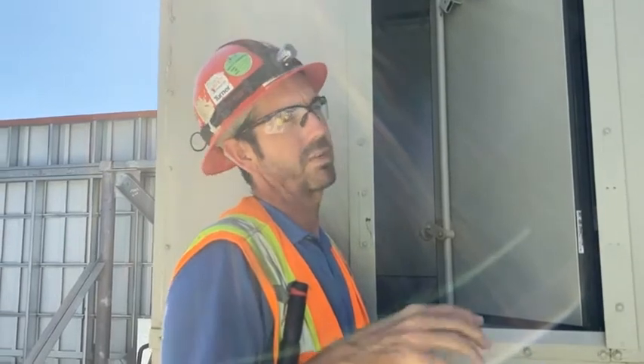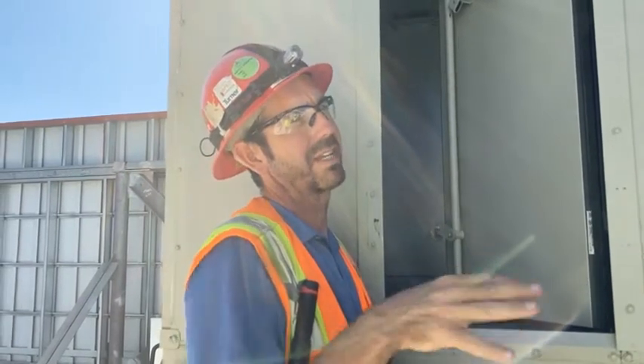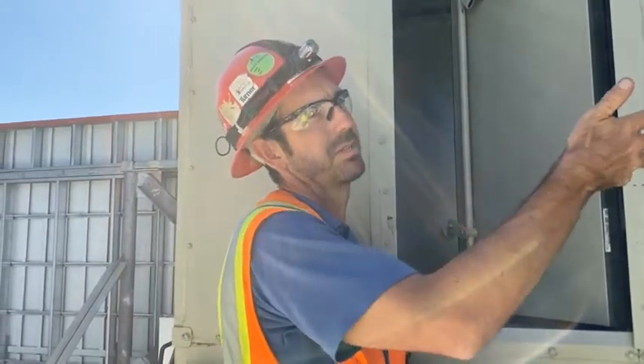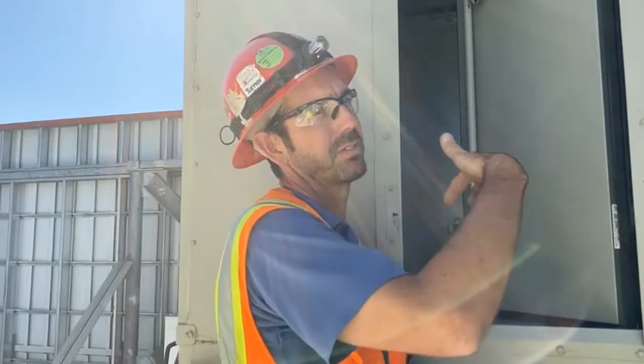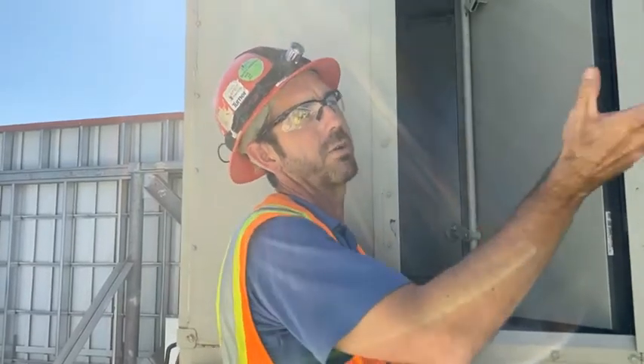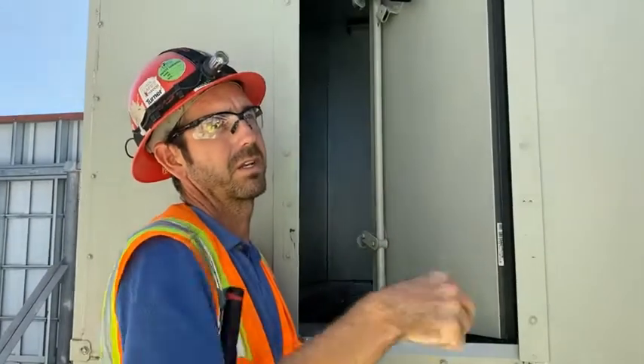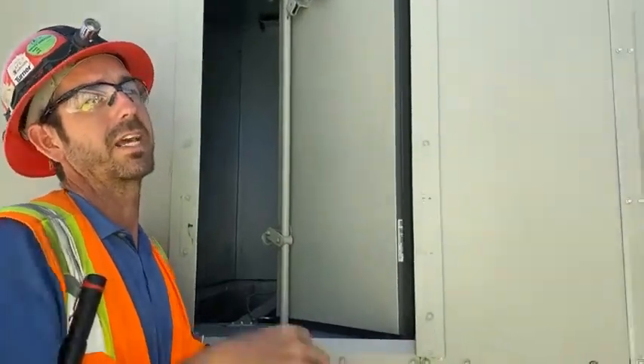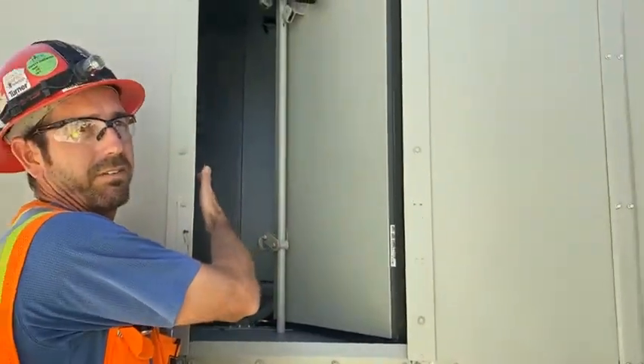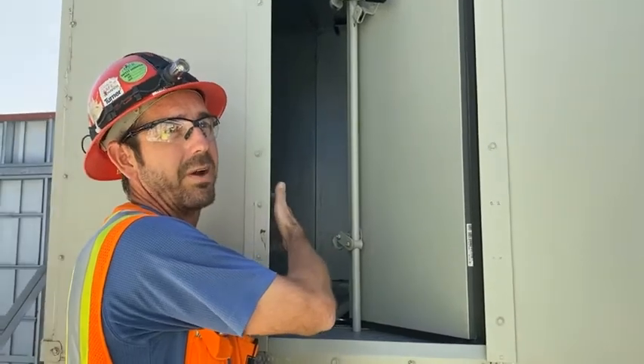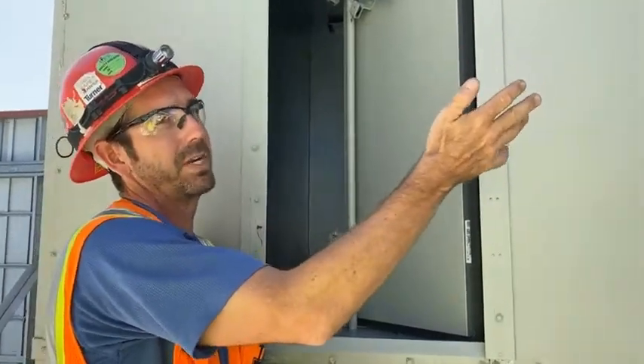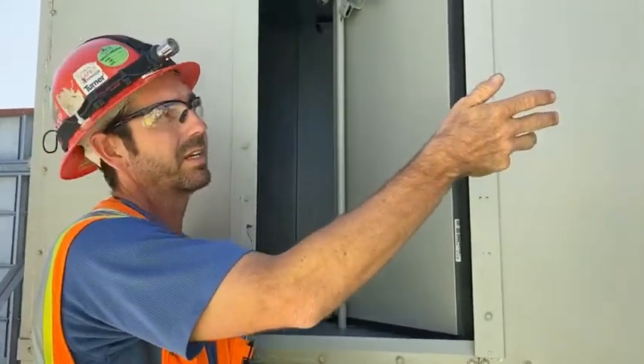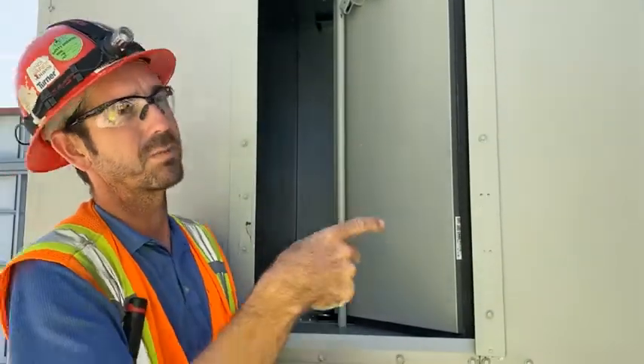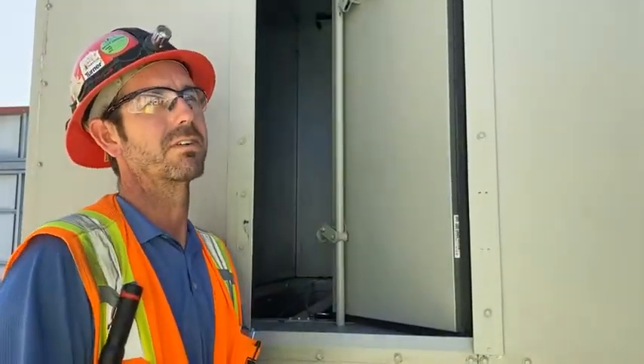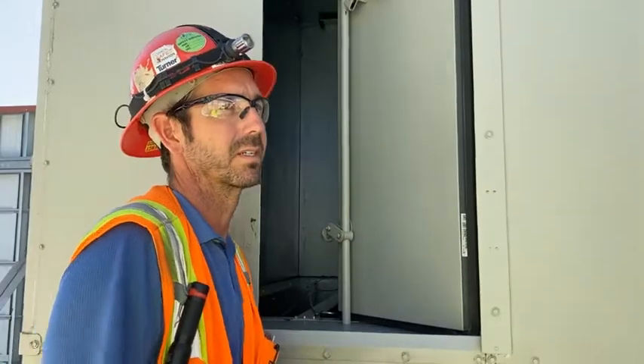We'll double check when you guys do your control checkouts. I don't think there's a low pressure since it's 100% outside air. Just high pressure switch. So if you have ductwork on the inlet, the static is controlled. I'm just saying this is here. I know what you mean. It is a high pressure cutout. I don't believe we have a low pressure cutout because it's 100% outside air. But there could be since there's dampers. We need to work with Doug and controls and verify that. Or we could open one of the doors and look again. Okay?